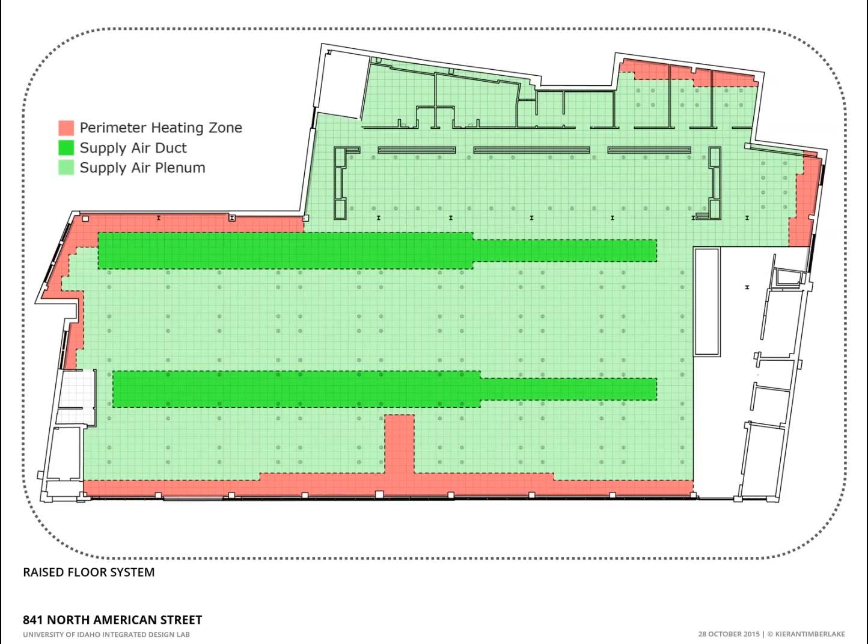So the idea here is that we have an underfloor system with two primary highways represented here and here. And those two would deliver a pressurized air through the underfloor system that will come out through a number of swirl diffusers that are located at every individual's desk. This is an unconventional system, one that would be combined with a night flush cycle that would deliver air through the underfloor system to cool down that slab and basically charge a thermal battery that could taper temperatures throughout the day. That was the theory.